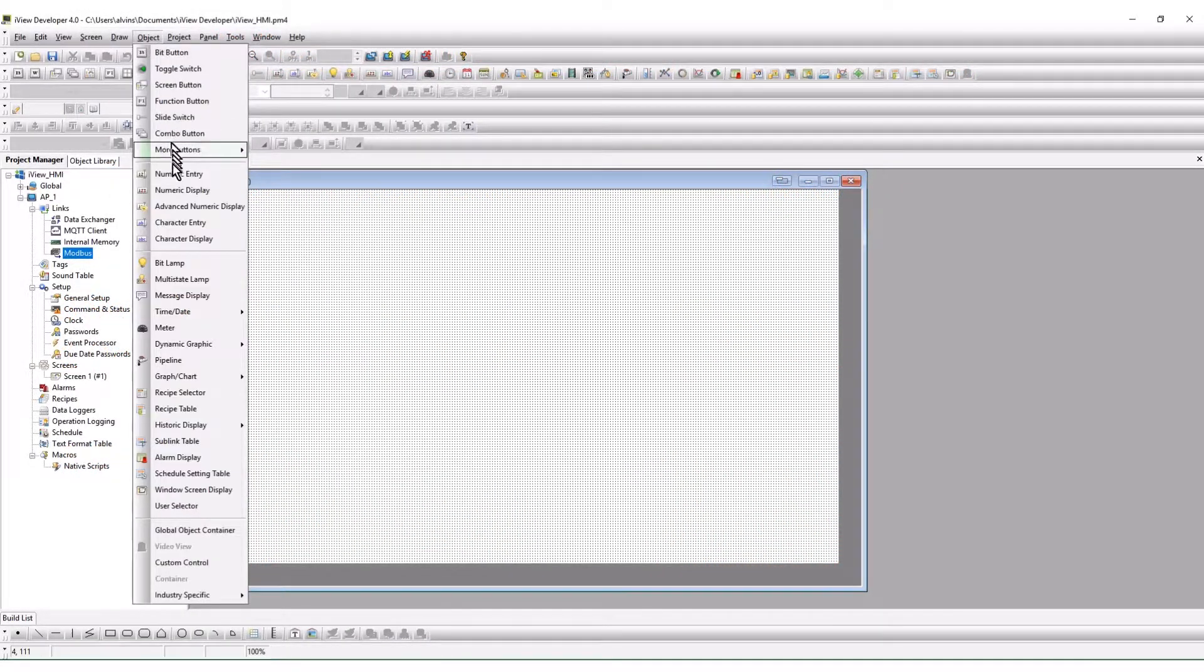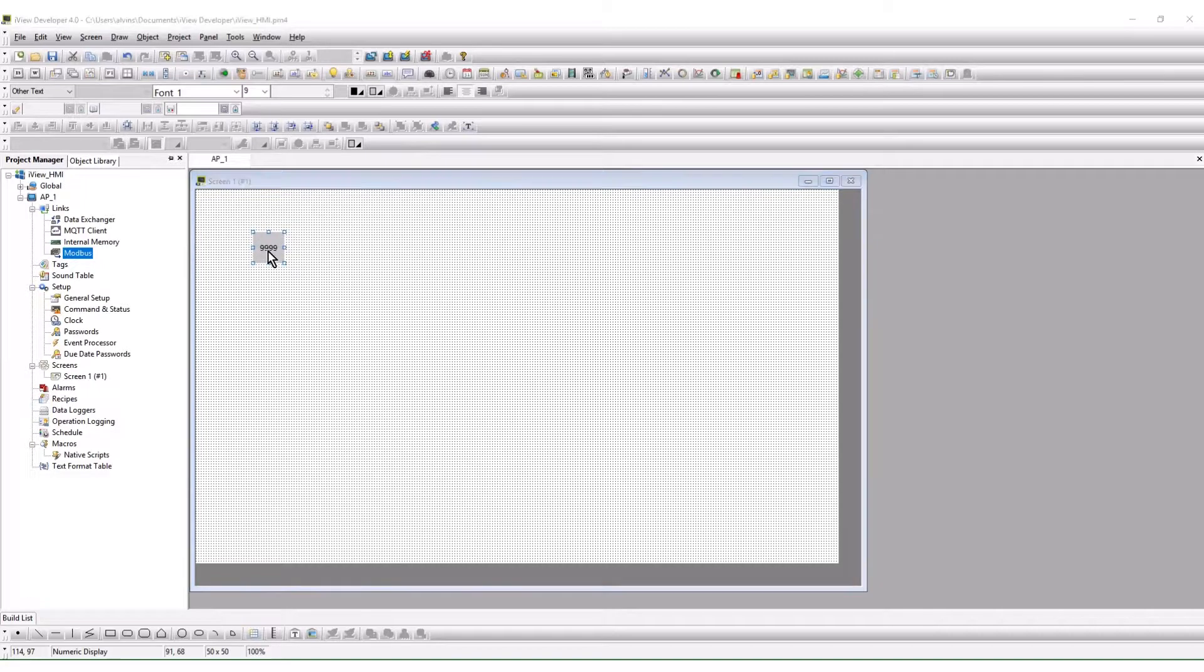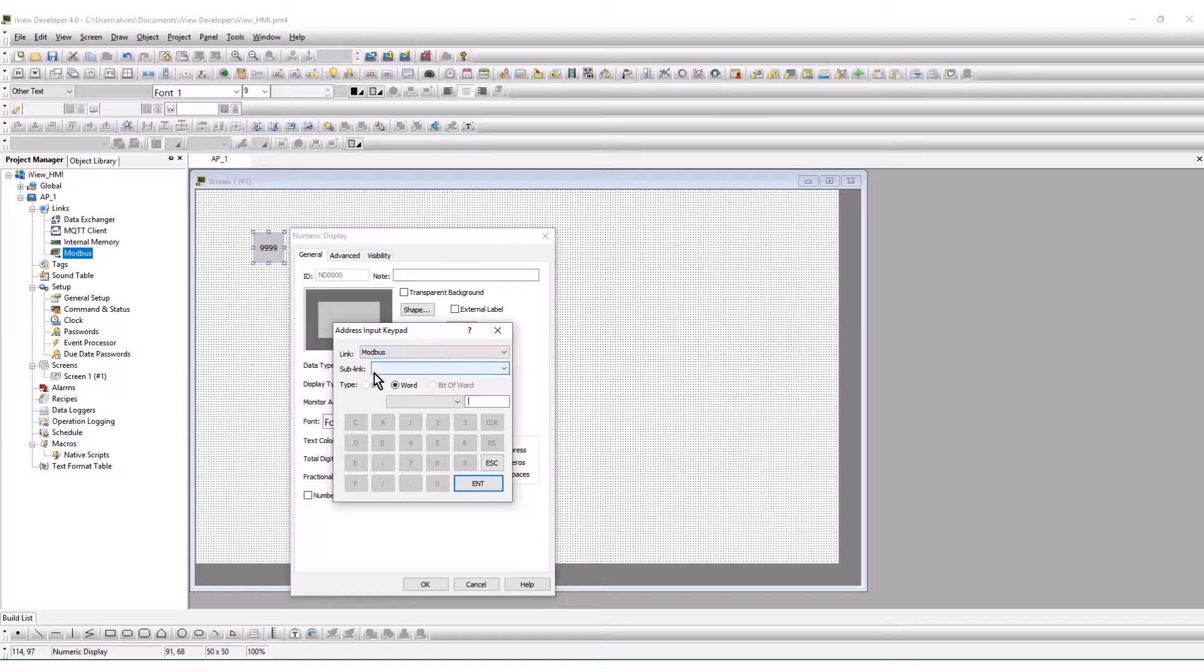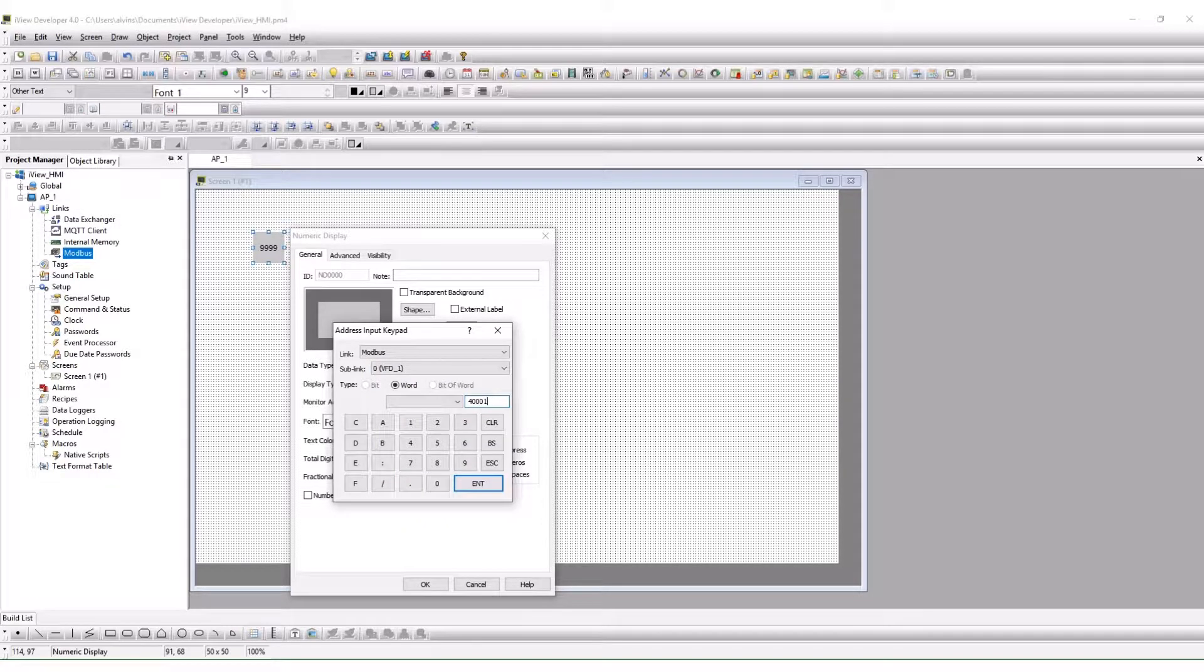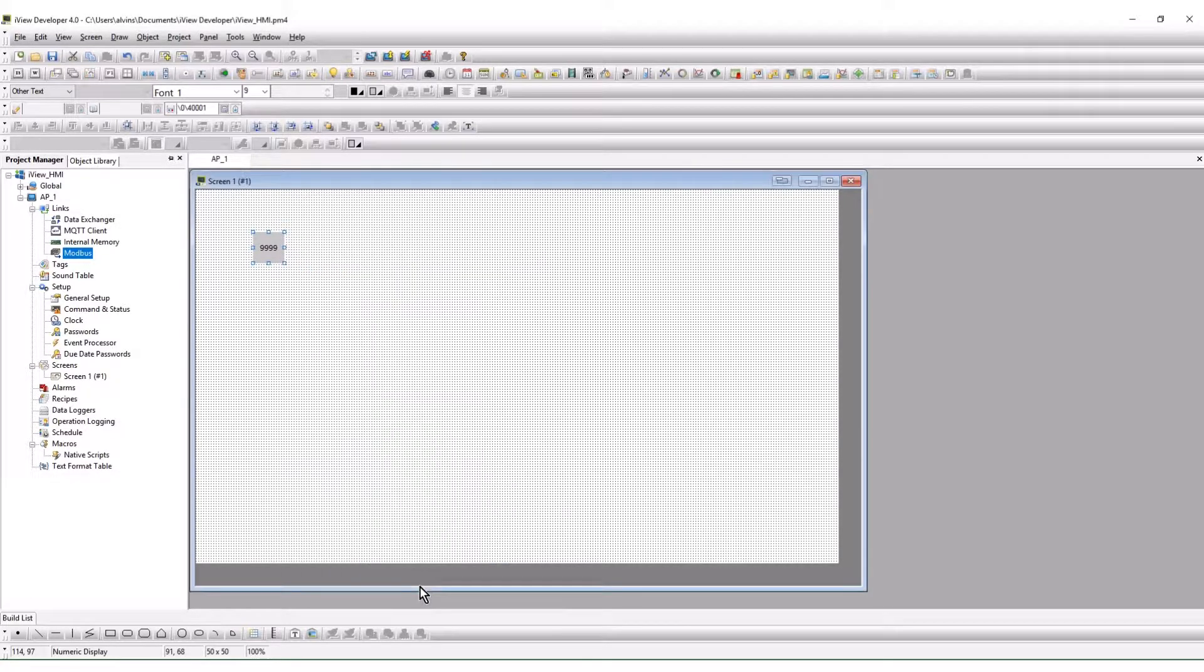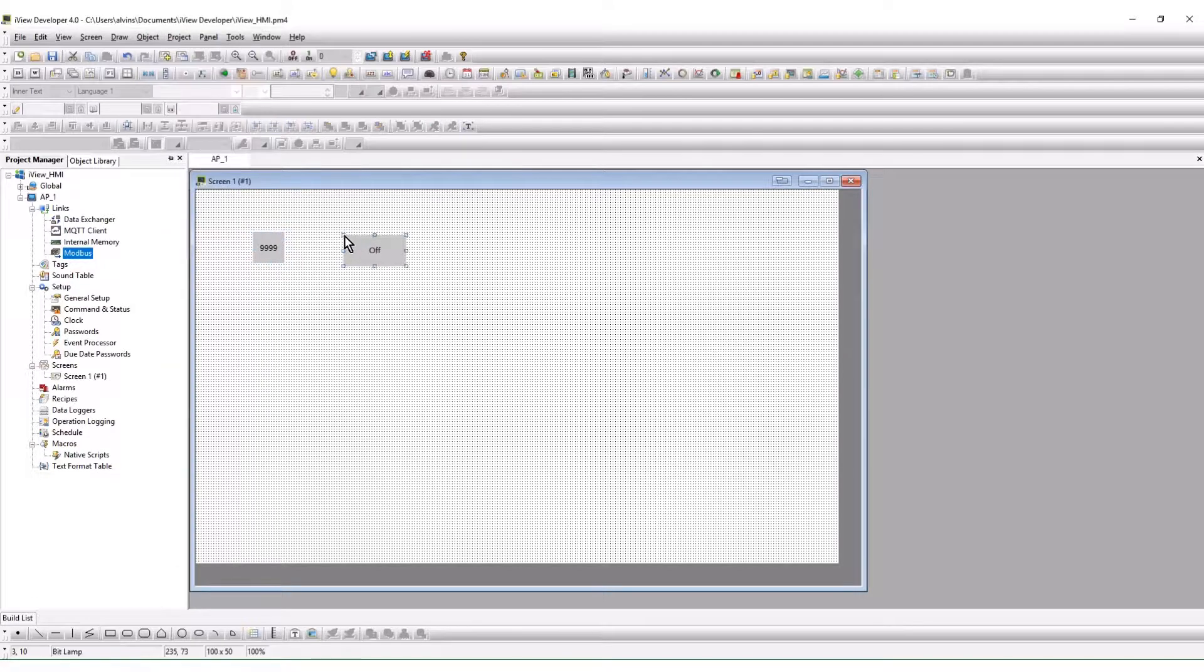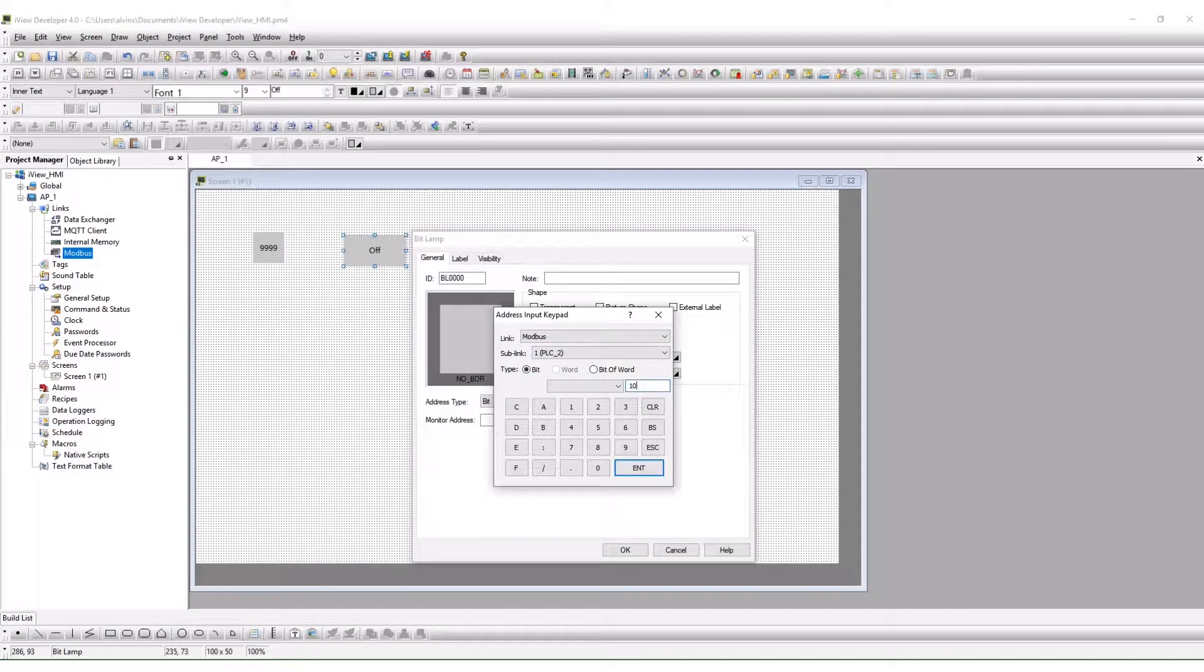Add a numeric display to the screen. When adding an address to the object, the Modbus link is selected. The sub link pull down will appear. Select VFD1. Input 400001 for the address. Use the same steps for adding a lamp monitoring PLC bit 100001.